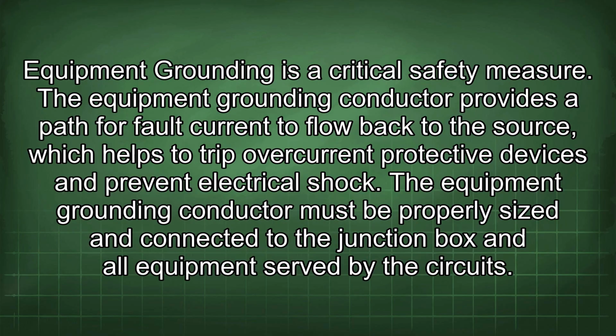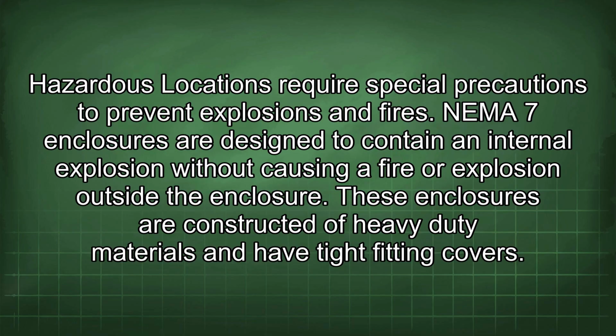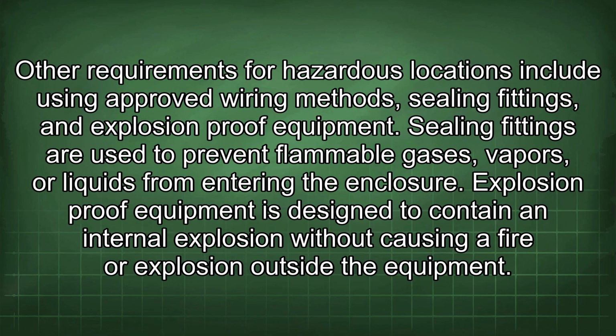Equipment grounding is a critical safety measure. The equipment grounding conductor provides a path for fault current to flow back to the source, which helps to trip overcurrent protective devices and prevent electrical shock. The equipment grounding conductor must be properly sized and connected to the junction box and all equipment served by the circuits. Hazardous locations require special precautions to prevent explosions and fires. NEMA 7 enclosures are designed to contain an internal explosion without causing a fire or explosion outside the enclosure. These enclosures are constructed of heavy-duty materials and have tight-fitting covers. Other requirements for hazardous locations include using approved wiring methods, sealing fittings, and explosion-proof equipment. Sealing fittings are used to prevent flammable gases, vapors, or liquids from entering the enclosure.